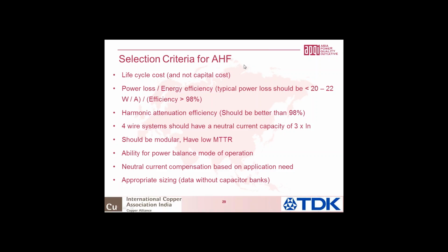And to sum it up, we know, as we just saw, there are lots of solutions available for reactive power compensation under harmonic-rich environment. The solutions can be simple capacitor banks, detuned capacitor banks, partially tuned banks, and active harmonic filters. The optimal choice must be based on a detailed system study and customer requirement analysis. The selection should be based on life cycle cost and not just capital cost. And tariff-related tools should address true power factor and not displacement power factor.